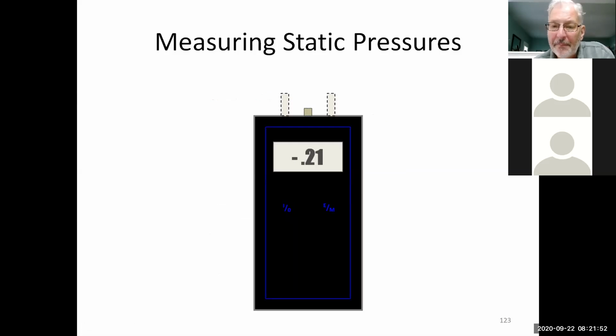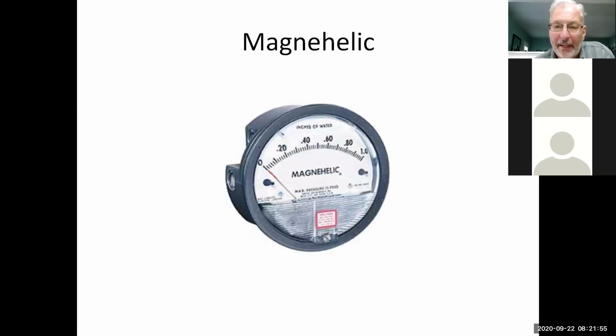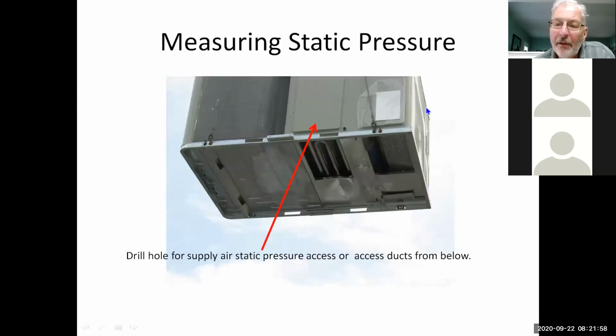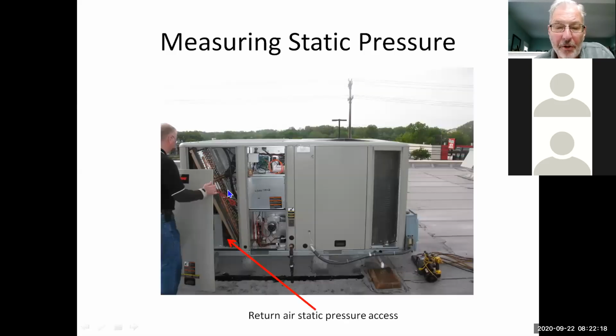Same thing, same process. We take a static pressure reading, and again, whatever gauge works for you. The Precedent is a little bit different. So in order to get static pressure on a Precedent, you have to get at the ductwork, or you can get to this plate on the end of the heat exchanger and drill a hole in here. Again, don't hit the heat exchanger. But if you drill a hole in here, that'll give you your supply static. And then on the return, if you get into this panel right here, in this compartment, drill a hole in that panel, you can get a return static on there too. So you can get your supply and your return pretty easy, even on a Precedent unit.